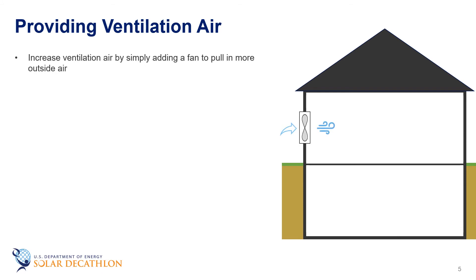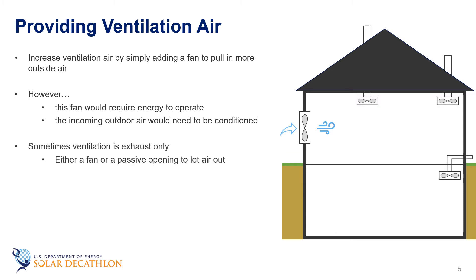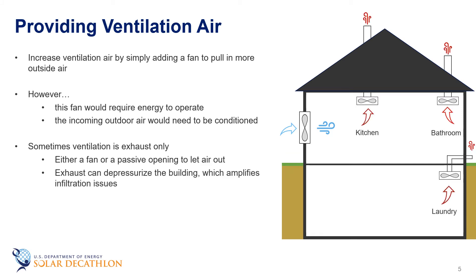The bottom line is that we need to increase the ventilation air. We can just add a fan and bring in more outside air, but remember, not only does the fan use energy, but we also need to condition the outside air that comes in. Sometimes the ventilation is exhaust only. For this, we would either need a fan to remove some air or create a hole in the building and let some air out. Bathroom fans, dryer vents, and range hood vents all extract air from the building.